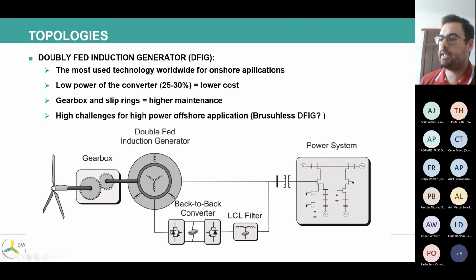The power converter in this technology is connected to the rotor, while the stator is connected directly to the grid. This is the most used technology worldwide for onshore applications. 80% of all onshore applications use this doubly fed induction generator. When you look at the whole installations, 50% is from doubly fed induction generator. So it's widely spread, because it has the advantage of low power of the power converter.